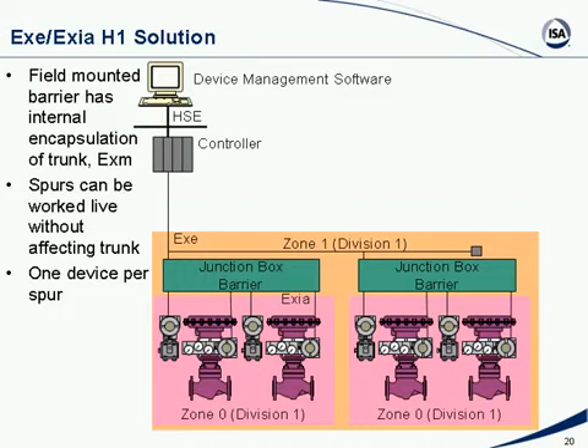Okay, so if I use a field-mounted barrier, I have an Ex e increased safety trunk with intrinsically safe spurs. I can also use this in Zone 2 if I like. Okay, in that case, I would have a non-arcing or non-sparking trunk and non-incendive spurs. Okay, so that's a solution ideal for Zone 2. Both intrinsic safety and non-incendive allow me to do live work on these spurs. Okay, so I can remove and connect devices live, which is very good for maintenance, obviously.